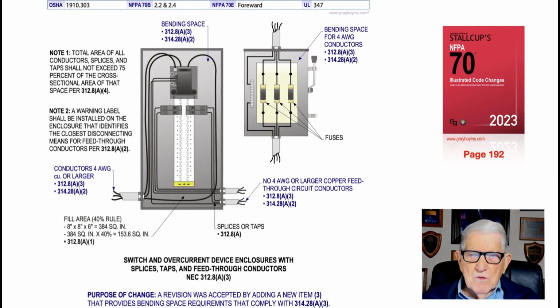Now this illustration deals with switch and overcurrent protection device enclosures where splices, taps, or feed-through conductors are present. And basically the purpose of the change, they just added a new item 3 that addresses these requirements where you might have an S-bend, as you see on the panel board. We come in, bend, come up, and bend again, and come into this terminal, this breaker. That's an S-bend. And then, of course, the circuit breakers that you see below the main circuit breaker, those are L-bends coming in from the enclosure. The disconnect switch to the right, L1, L2, and L3, notice those are Z bends.